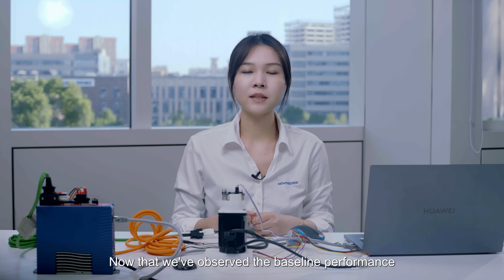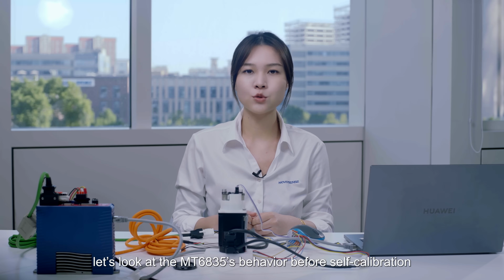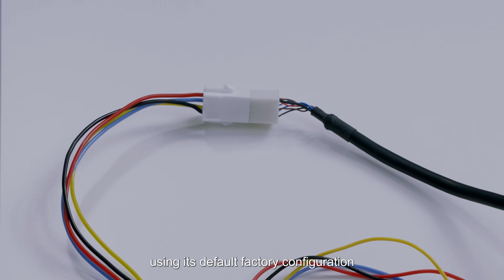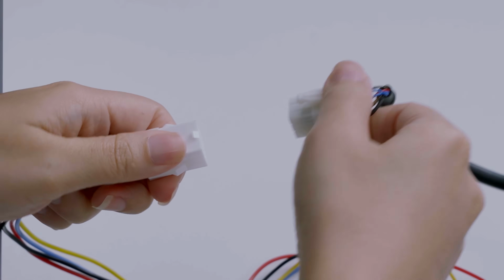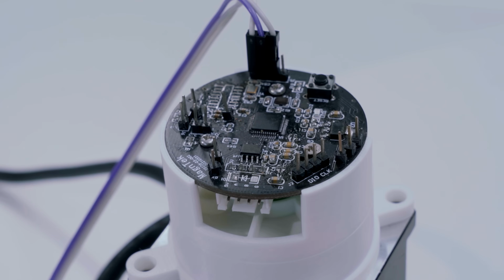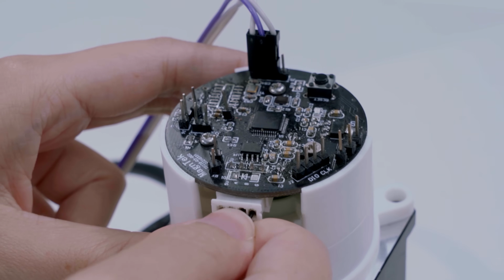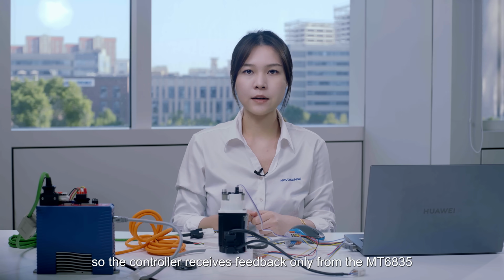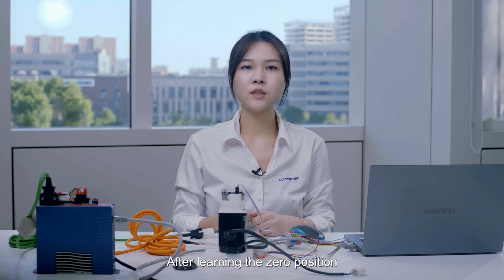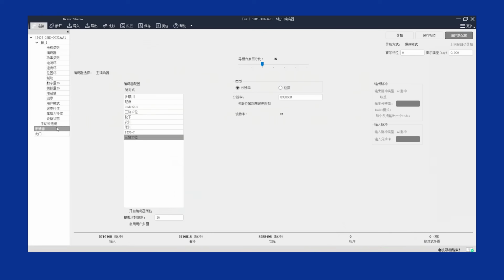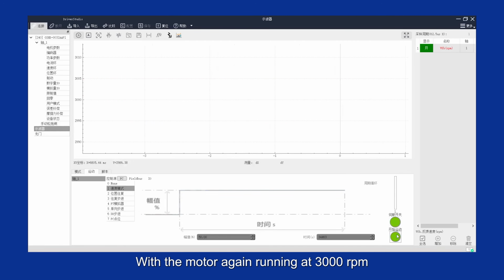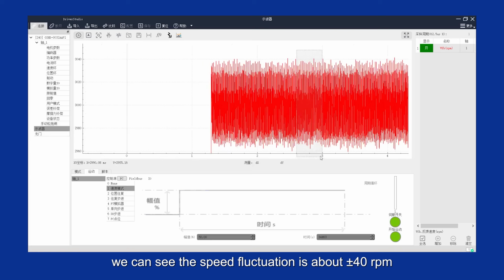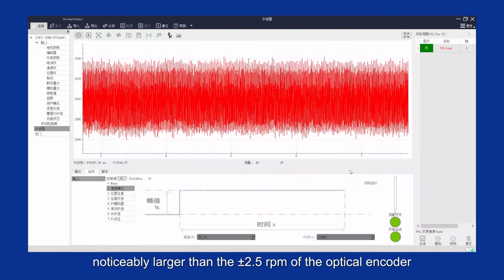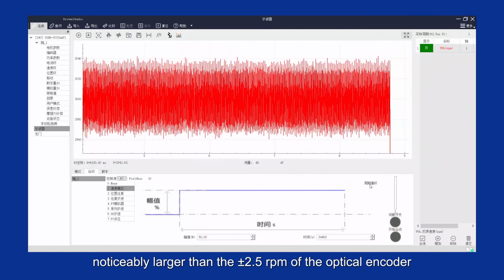Now that we've observed the baseline performance, let's look at the MT6835's behavior before self-calibration, using its default factory configuration. We disconnect the optical encoder feedback so the controller receives feedback only from the MT6835. After learning the zero position, we check its speed stability. With the motor again running at 3000 revolutions per minute, we can see the speed fluctuation is about plus or minus 40 revolutions per minute, noticeably larger than the plus or minus 2.5 revolutions per minute of the optical encoder. This is the MT6835's performance without self-calibration.